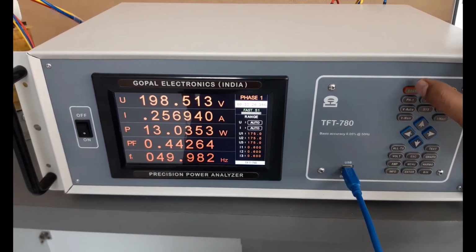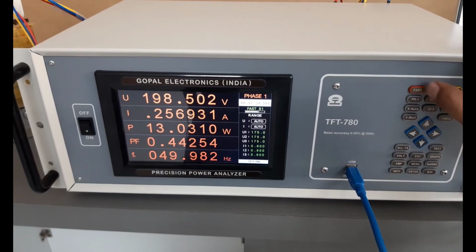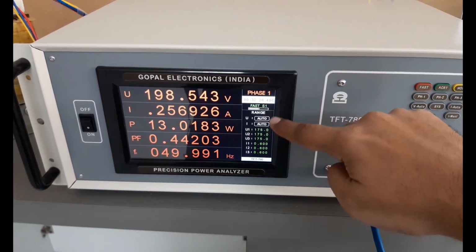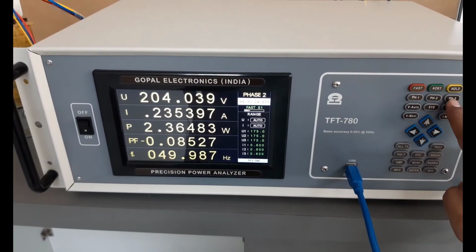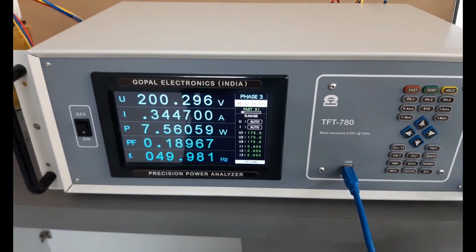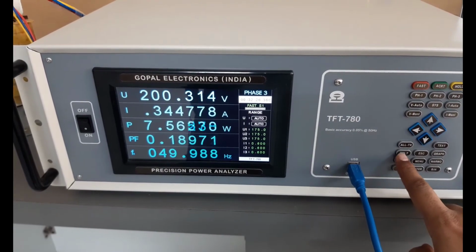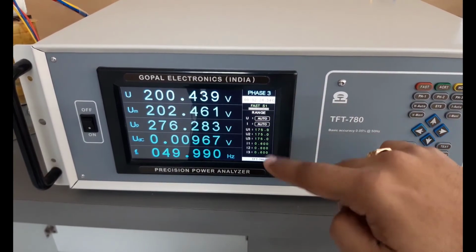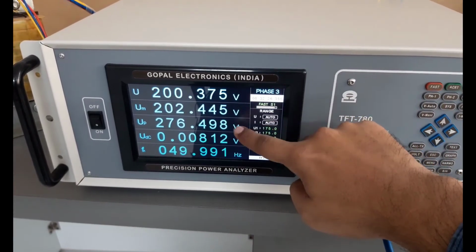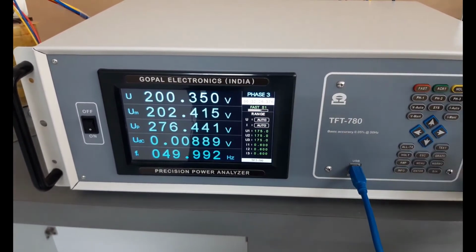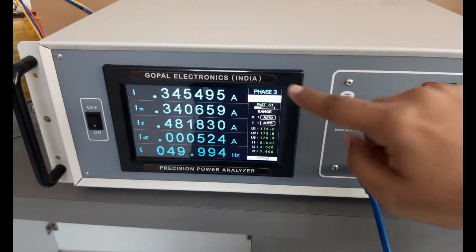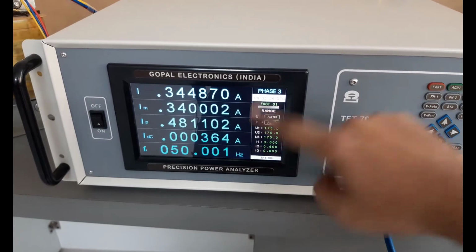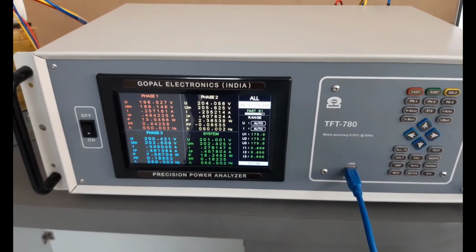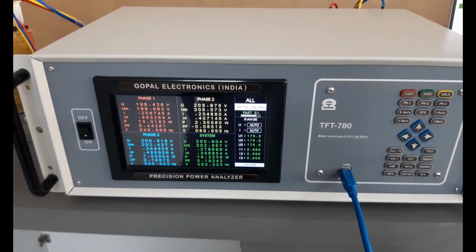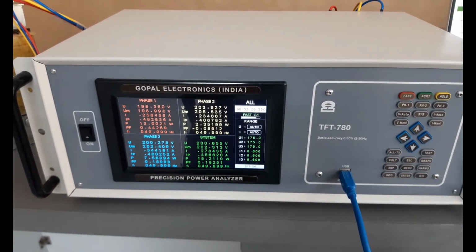Now I will put this equipment in a fast measurement speed. Now this is displaying phase 1 parameter, phase 2 parameter, phase 3 parameters. While keeping phase 3, if I press volt, it will display voltage parameter like RMS volt, mean volt, peak volt, UDC and frequency. Same way for current parameters, RMS current, mean current, peak current and frequency. While pressing all text mode, it will display all parameters in a single display for phase 1, phase 2, phase 3 and system.